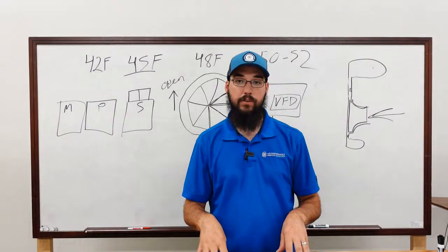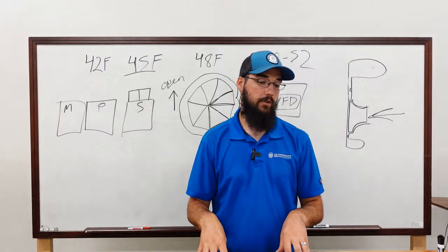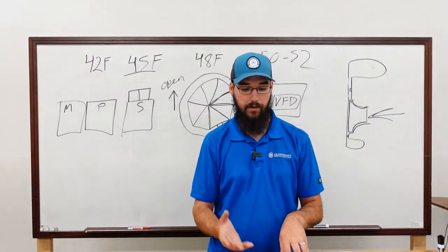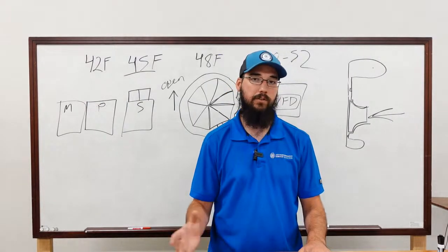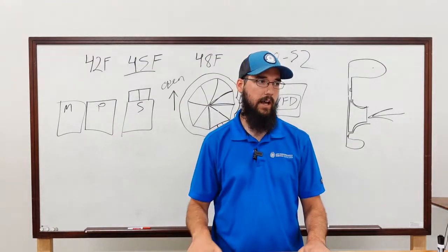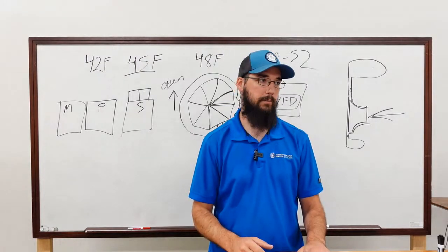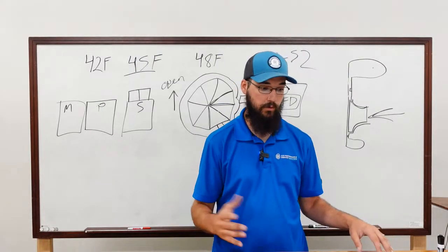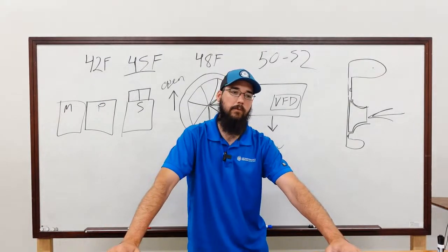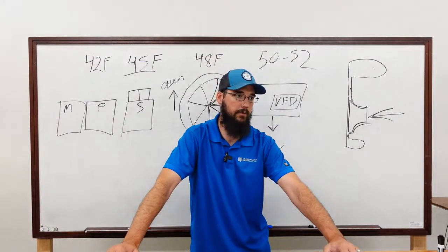Anyway. The recovery port is going to be on the bottom of the chiller. If you walk up to a water-cooled chiller, you'll see coming out the bottom of the evaporator that there is a port, it could be 5/8, it could be half inch. I think most of them are half inch, but whatever the size is, you'll have a big port coming out. A lot of times it may even just literally be a ball valve. Now it's not just a regular Home Depot ball valve, but it'll be a ball valve that you can open and close to recover that refrigerant. And you can hook up whatever machine you like to that, just adapt it down however you do it.